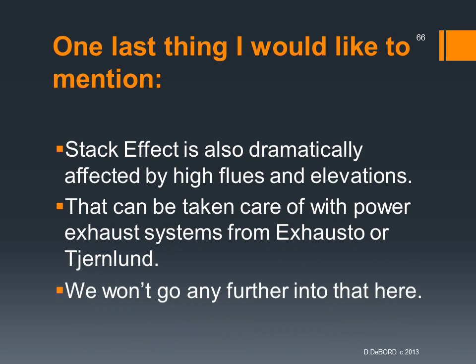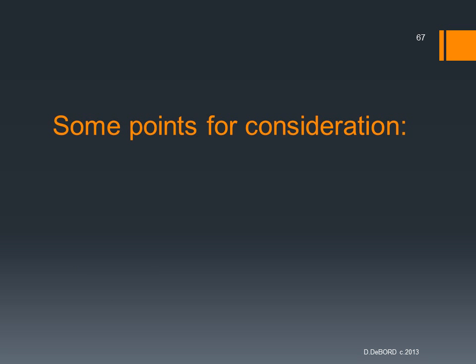One last thing I'd like to mention as far as height goes: stack effect is also dramatically affected by high flues and elevations. We can take care of a lot of this with powered exhaust systems from people like Exhausto or Tjernlund, but we won't go into that any further right here. Remember that the flues always have to be coordinated with the HVAC because they're providing the air. You get the combustion air in the exhaust from HVAC, and all these things must be worked out together.